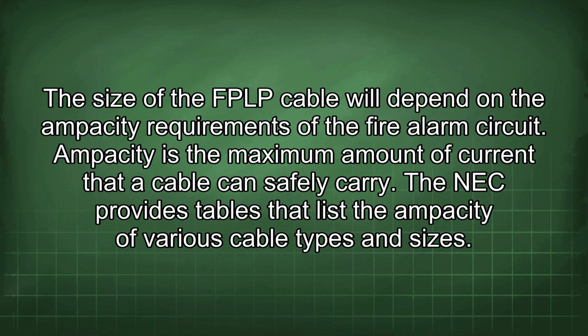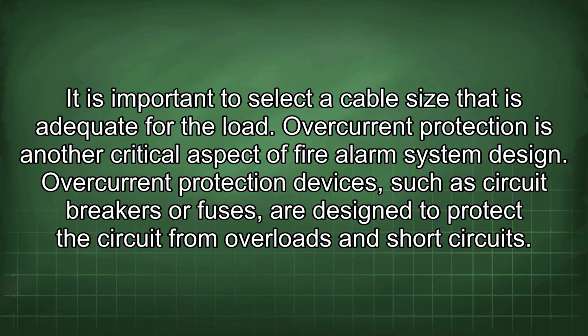The size of the FPLP cable will depend on the ampacity requirements of the fire alarm circuit. Ampacity is the maximum amount of current that a cable can safely carry. The NEC provides tables that list the ampacity of various cable types and sizes. It is important to select a cable size that is adequate for the load.